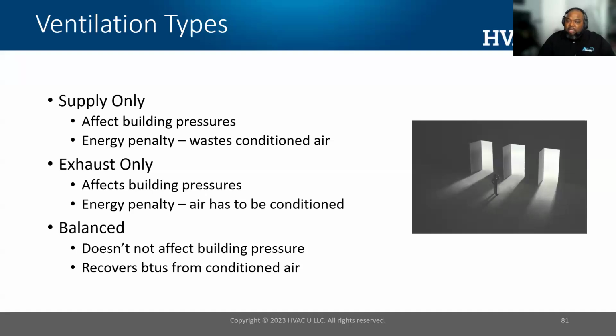Just to be clear, ventilation is not an energy efficiency evolution. It doesn't have a savings to investment ratio. It doesn't have a return on investment. It doesn't have a payback period. We joke and say that the return on investment is keeping you out of the hospital. So when we look at it, they typically take energy to run ventilation systems, and they're not necessarily an energy efficiency device.